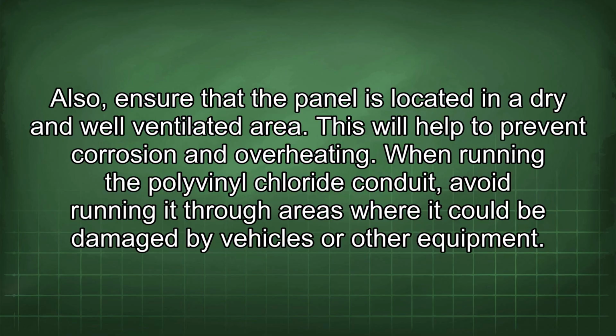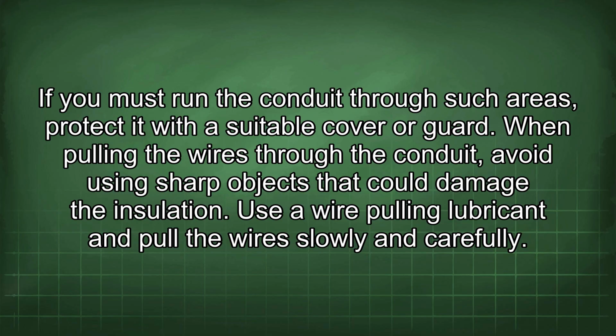When running the polyvinyl chloride conduit, avoid running it through areas where it could be damaged by vehicles or other equipment. If you must run the conduit through such areas, protect it with a suitable cover or guard. When pulling the wires through the conduit, avoid using sharp objects that could damage the insulation. Use a wire pulling lubricant and pull the wires slowly and carefully.